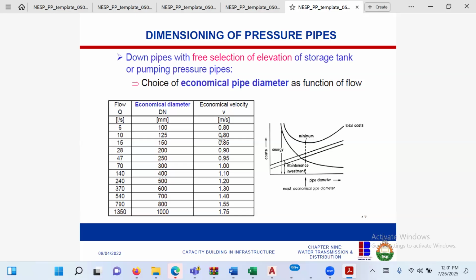After this lesson, those of you that are consultants, you need to change your design parameters. Because when I see many designs, I will see uniform pipe. It's not possible. Because the flows are not the same. As your water is moving downstream, the pipe size will reduce. As it's moving upstream, it's having more load, the pipe size will increase. So this uniformity of pipes is bad design.